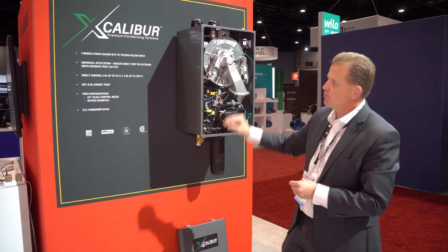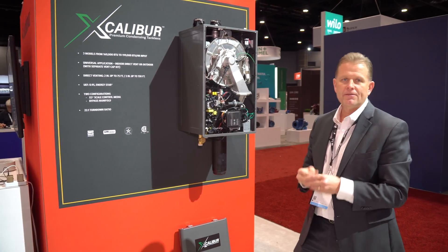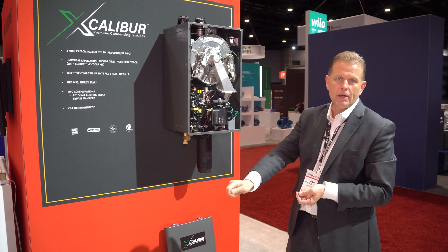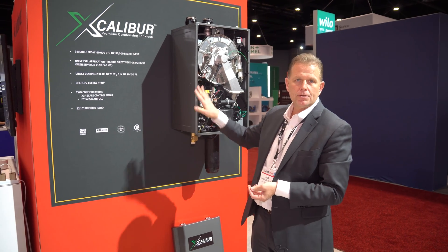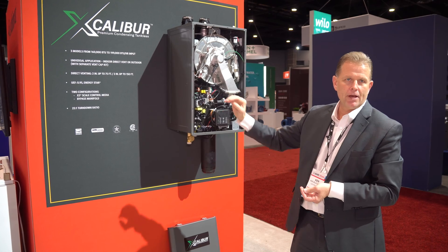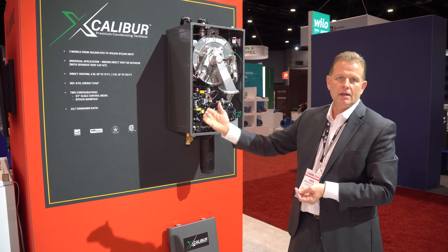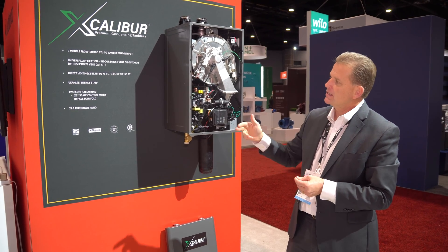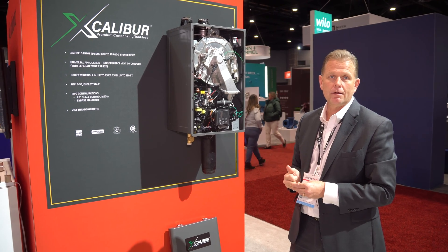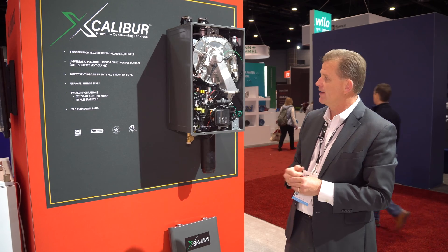Another major differentiator for this product is that it has a 22 to 1 turndown ratio. So in those very low flow conditions in your home — if you're only operating one hand sink — this unit can operate down to a 22 to 1 turndown ratio, a very small fraction of its total input. That is two times more than most tankless products on the market, which are typically around 10 to 1 turndown, so we've got a major advantage there.